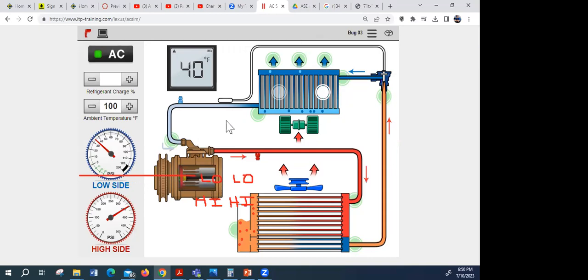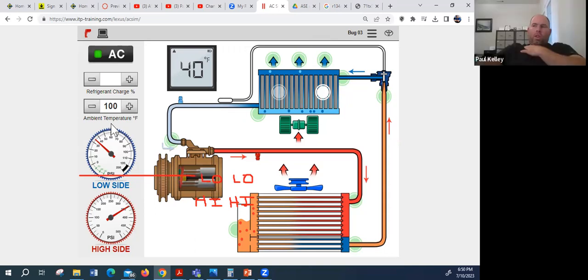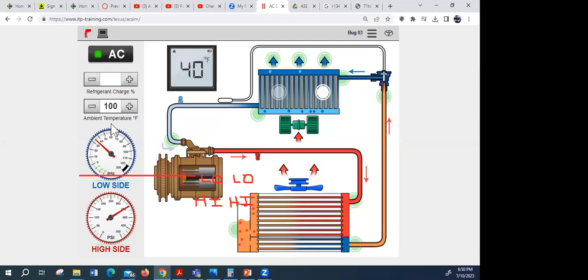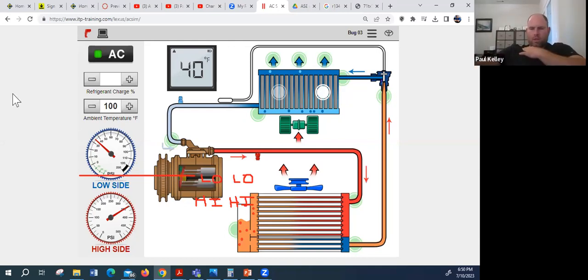And if there's air in the system, the pressures would be high. The low would probably be normal, but the high would spike up when the air hit the high side - not with a rhythm like a bad reed valve, but more like pop, pop, pop, pop, pop, almost inconsistent and erratic and crazy. But on the high side, you'll notice it.